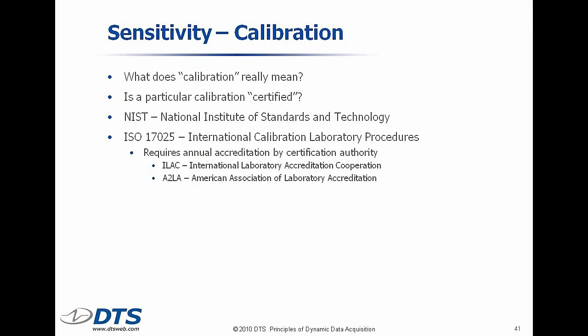So what about calibrations of transducers? I think you're going to get a chance to see some cool stuff out in the tour, but the term calibration really means comparing a reference known device to something that needs to be calibrated. And so one of the things that we use all the time is we use equipment that's been calibrated and perhaps certified to be accurate to the National Institute of Standards and Technology. And we do that all the time. Our shop is full of instruments that were calibrated to it and certified that they're accurate. So all that really means, whether it's a sensor or a data acquisition system, is you compare known inputs with the unit you're calibrating, and then you've got some tolerance and uncertainty.